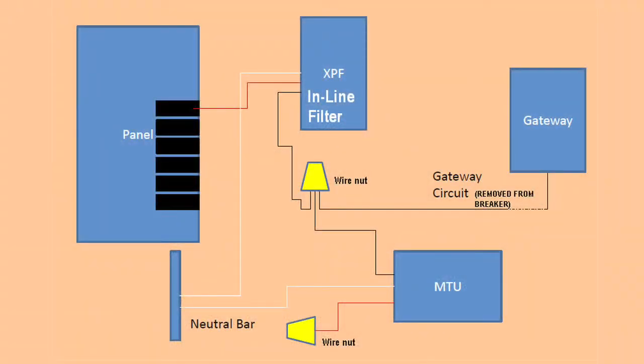For single panel installations, it's best to use the filter to isolate the TED system. For MTUs installed in multiple panels, you will need to power the MTUs from the same breaker to be able to isolate the TED system with an inline filter.